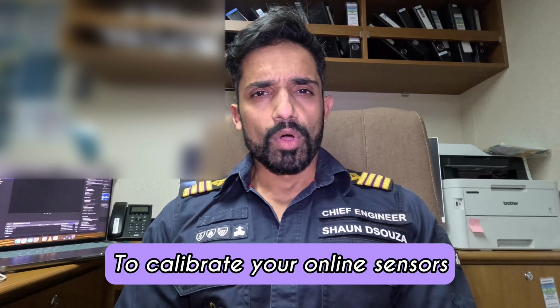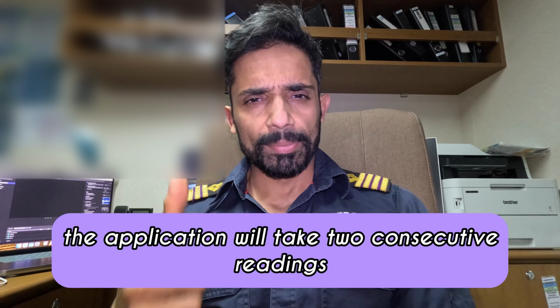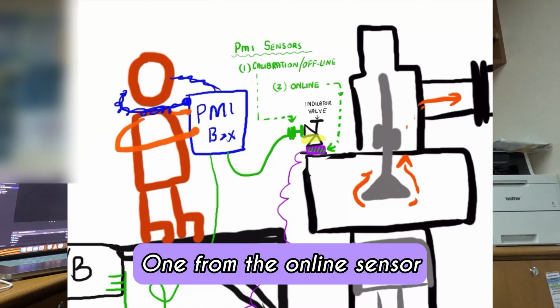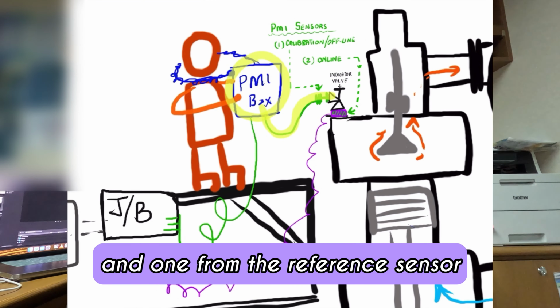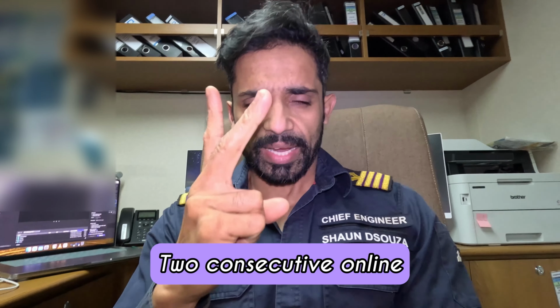To calibrate your online sensors, the PMI software application will take 2 consecutive readings, one from the online sensor and one from the reference sensor, 2 consecutive, online and reference, and then give you the graph. And once there's no discrepancy in the graph, you see everything is all right, and that's when we proceed to the next one and accept that particular reading.